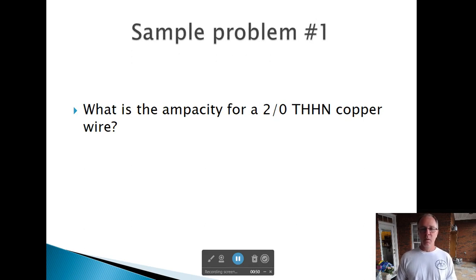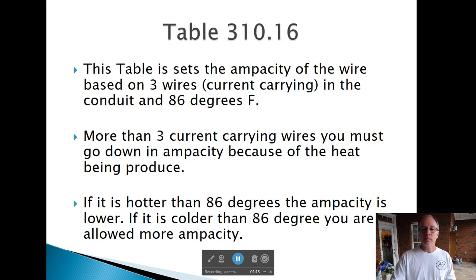Problem number one. What is the ampacity of a 2-Aught THHN copper wire? We've got 2-Aught as the size, THHN as the type of insulation on the wire, and it's copper. Those are the three things we need to know to find out the amperage. So we're going to go to Table 310-16. Table 310-16 is based on there being only one, two, or three current-carrying wires in that conduit or cable and the ambient temperature around that is 86 degrees.